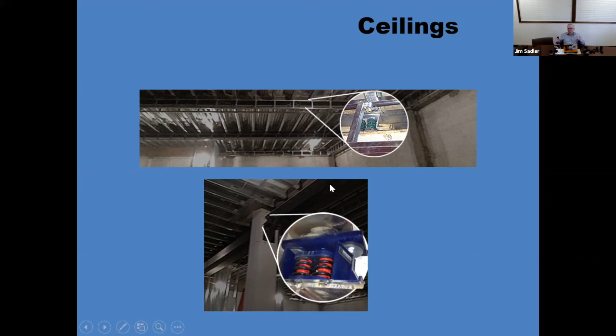So what we did in this case is we used the columns and designed a steel gridwork, and it was supported not by hangers, but by more floor supporting isolators. So they built haunches into the column. Those isolators are placed on top. They built a steel framework, and then they attached the ceiling to the steel framework. So an isolated ceiling supported from below. So there's always a way.